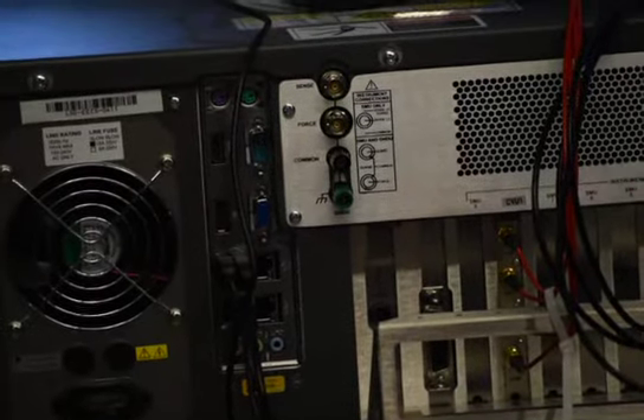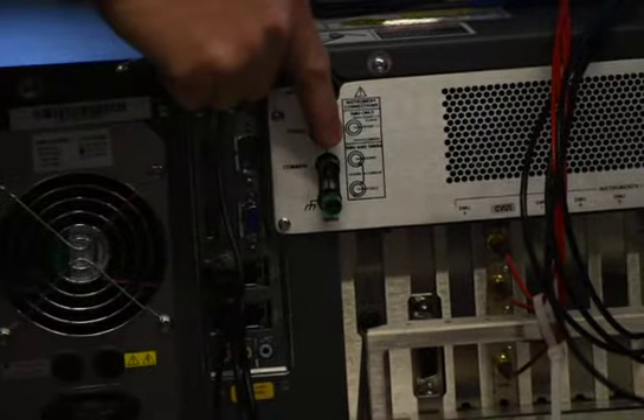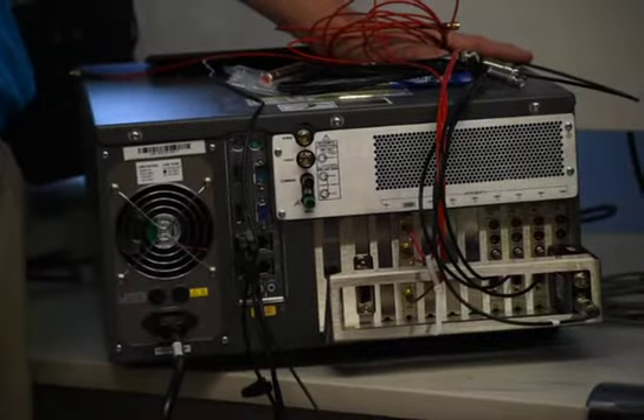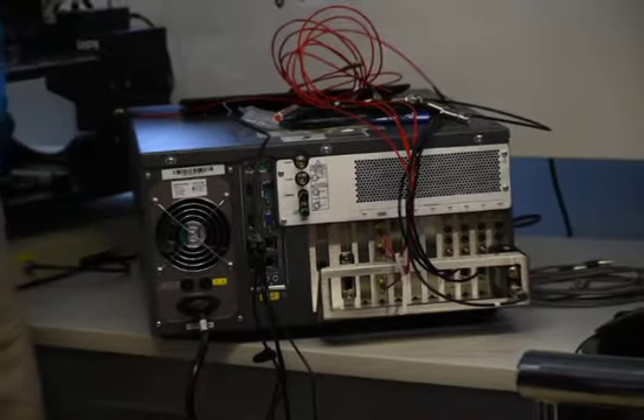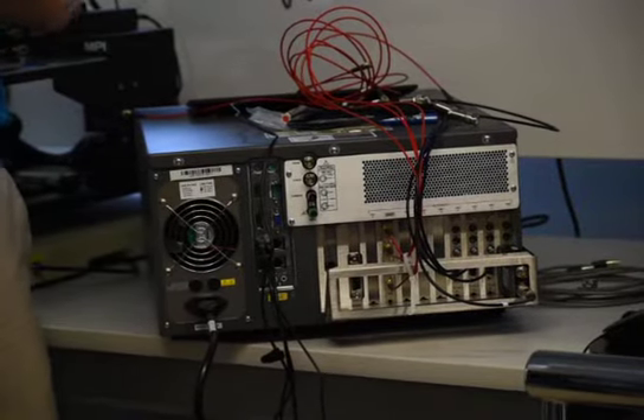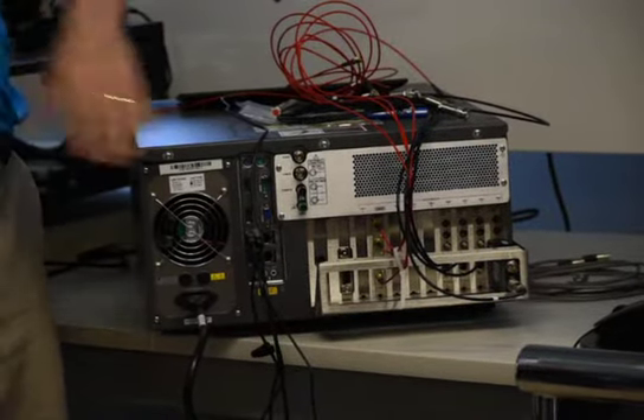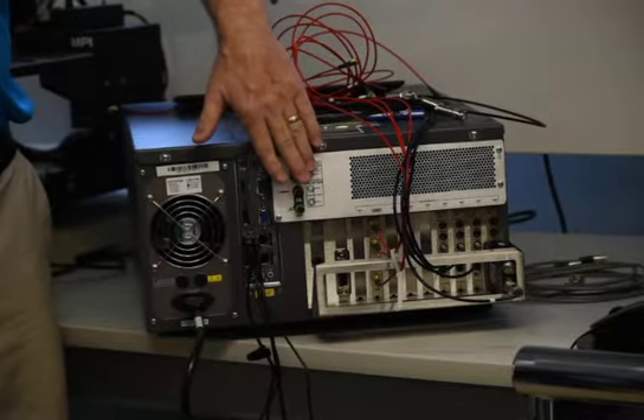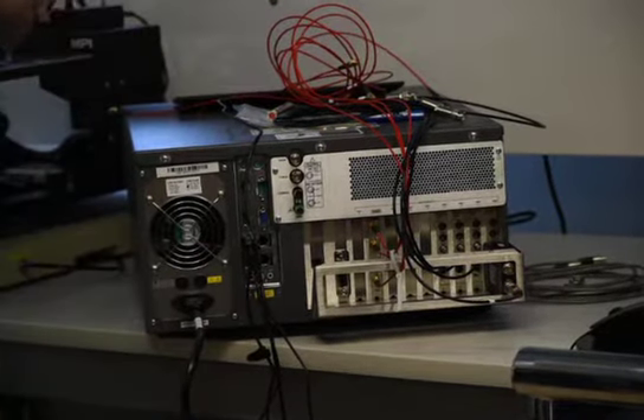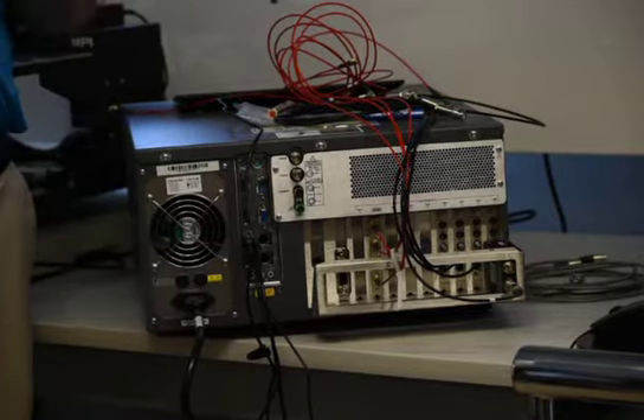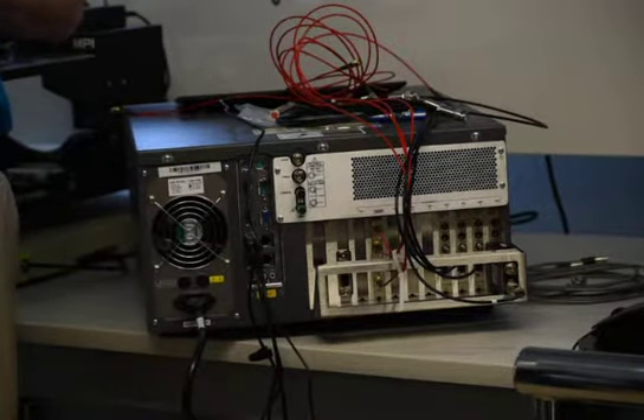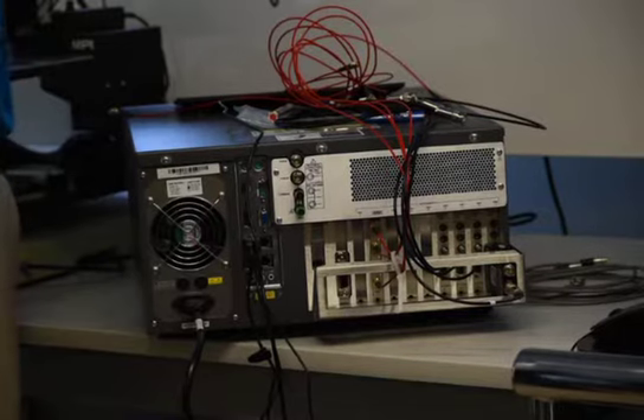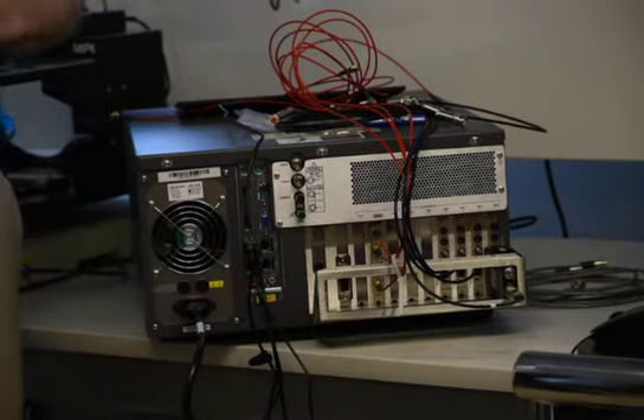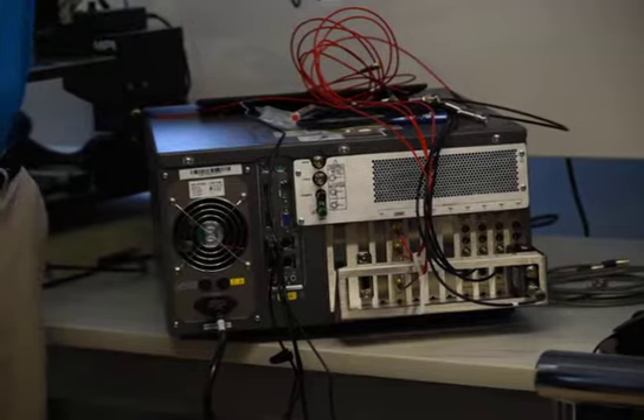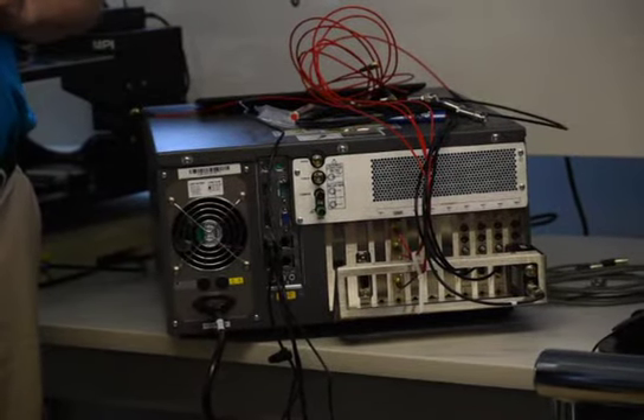A lot of people, to save money, if they need to do 4 terminals, will buy 3 SMUs and use the ground unit for the 4th ground. You almost always have a ground on your device. But the SMU is better at ground than the ground unit is. So since you have 4 SMUs, pretend this doesn't exist. You don't need it, because your best accuracy is always on the lowest range. The ground unit doesn't have ranges; the SMUs do. So you can set the SMU to a very low voltage range, source 0 volts, and have a very good ground. If you had it on a high voltage range and sourced 0 volts, you're not going to have a good ground. So just so you know that.